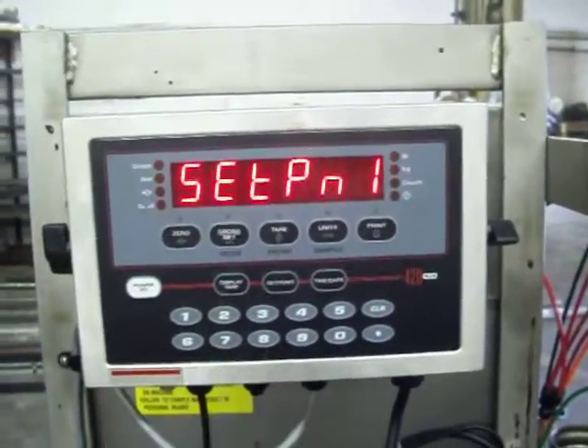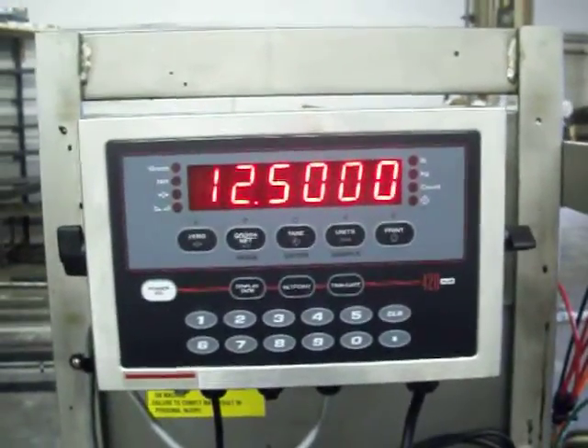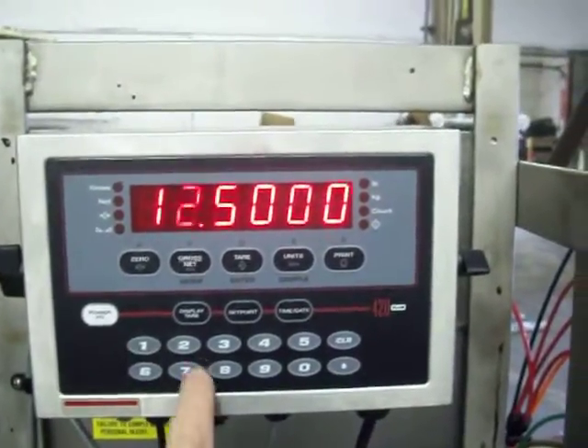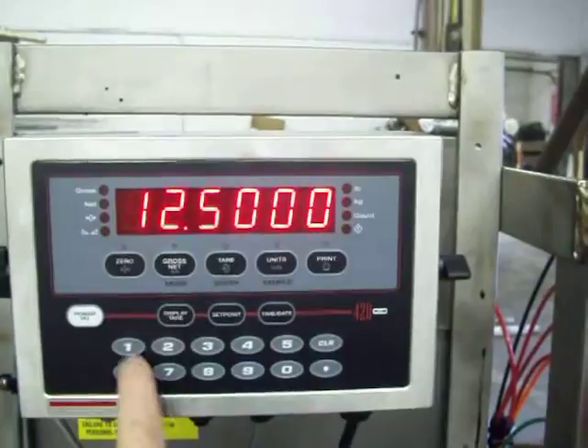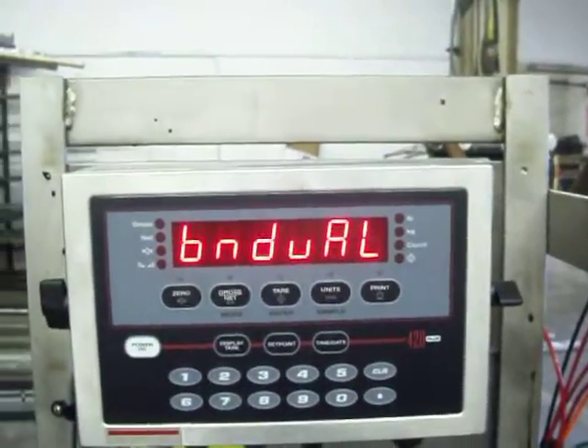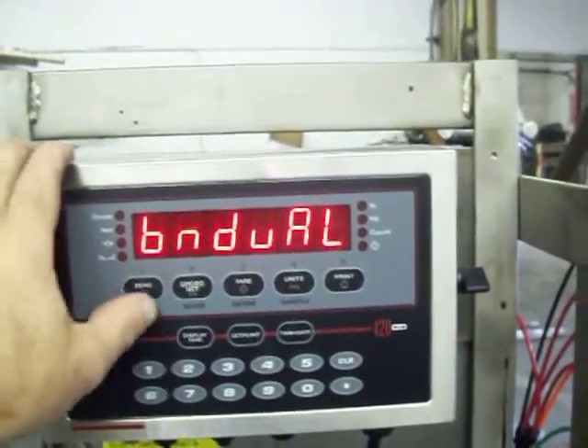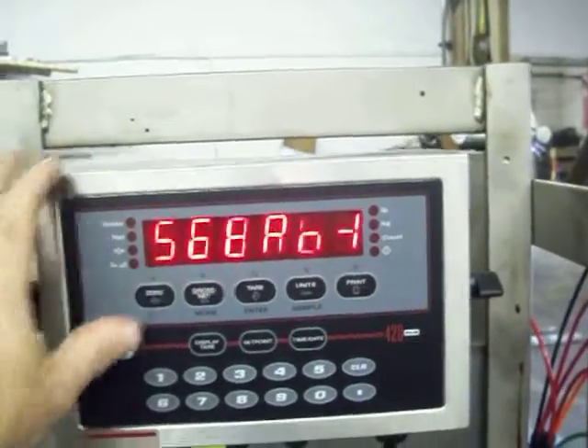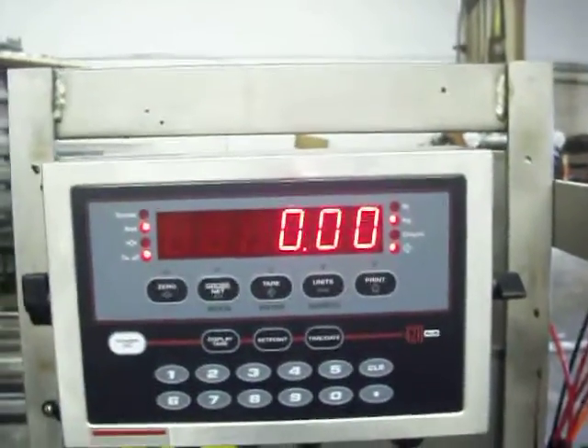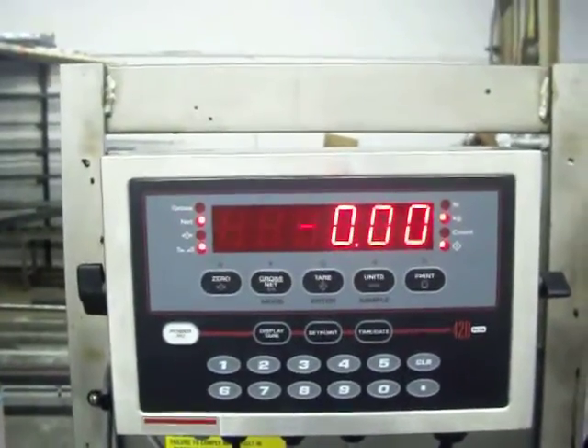We're going to do that and it'll show you the current value that's in the indicator. Right now we have 12.5 kg. Now if I want to change that, I can simply enter in the value that I want. We'll go 12.6 and you'll press enter, which is also the tare key. Then it'll show BNDVAL. For our purposes, we do not change that. Once I've entered it, I hit the up key twice — that's also the zero key. There's a triangle indicating up. Once you've hit that, it'll go back to its normal value. Right now we're just sitting at zero with nothing on the scale.